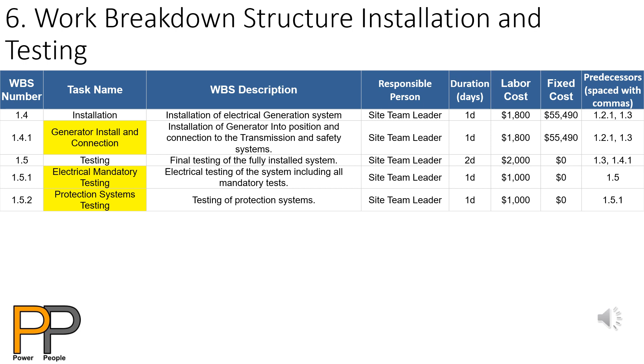The last package is 1.5 testing, with 2 activities: 1.5.1 electrical mandatory testing and 1.5.2 protection systems testing. This ensures the system complies with electrical standards and regulations and operates as intended, and that if faults occur, the safety system will protect and operate correctly to reduce risk of harm to the villagers and the system. Once all packages have been completed, the project is finished and ready to hand over.